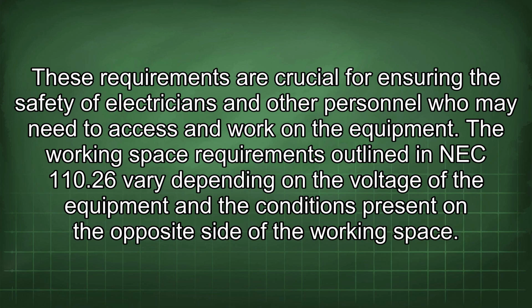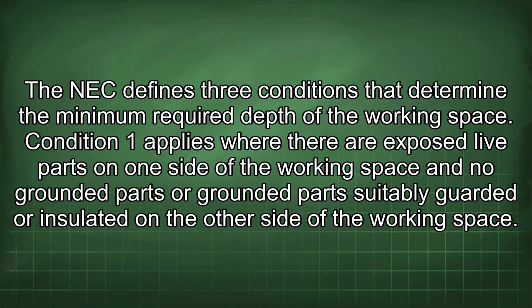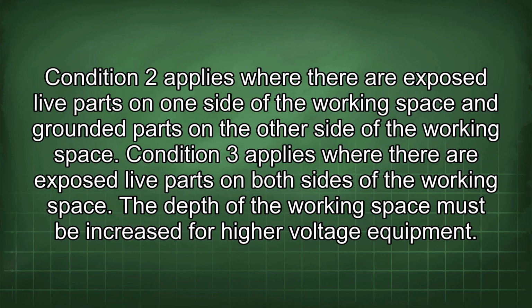The working space requirements outlined in NEC 110.26 vary depending on the voltage of the equipment and the conditions present on the opposite side of the working space. The NEC defines three conditions that determine the minimum required depth of the working space. Condition 1 applies where there are exposed live parts on one side of the working space and no grounded parts, or grounded parts suitably guarded or insulated, on the other side of the working space. Condition 2 applies where there are exposed live parts on one side of the working space and grounded parts on the other side of the working space. Condition 3 applies where there are exposed live parts on both sides of the working space.